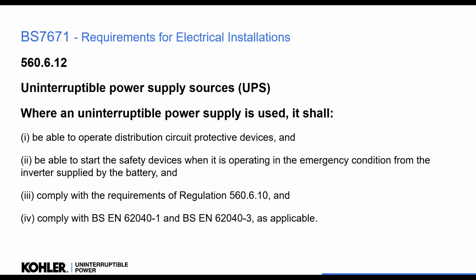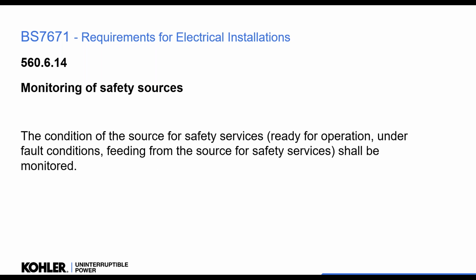Okay, so in island mode, with no mains available, we have to be able to trip the distribution and start the devices. The batteries have to comply with the relevant regulation, and the UPS must be built to standard 62040 part 1 and 3. Okay, so it's quite specific. It also says that the safety service should be monitored to know that it's available to be used when required.